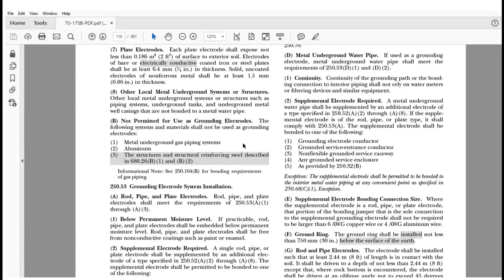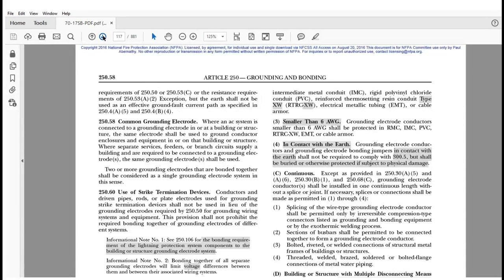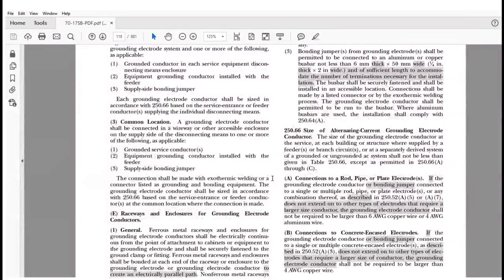All right, the next change is to 250.66, a much awaited change because of the confusion that it caused. For years, many people argued, what in the world was a sole connection? What did it mean? I think it was pretty obvious to many people. The words sole connection have been in the code since 1965, but it caused a lot of confusion. I have answered many a question through the years about sole connections. My intent always was that it's a sole connection to that electrode. If it goes on to an additional electrode that would require a larger size, then that was no longer the sole electrode connection. All right?